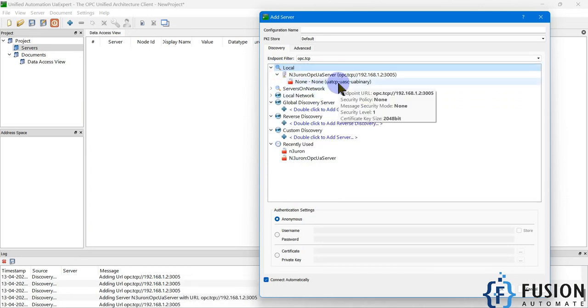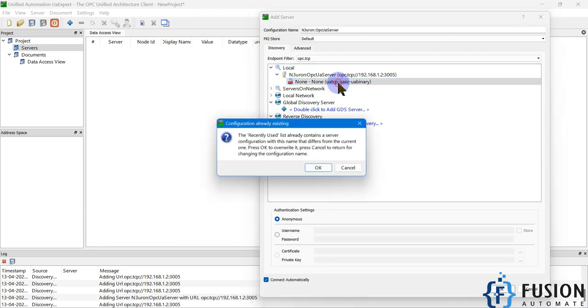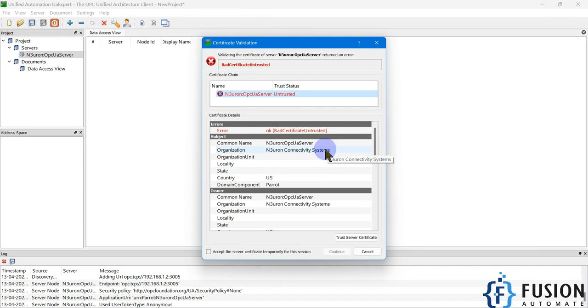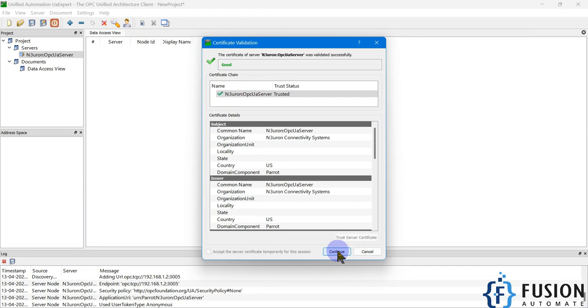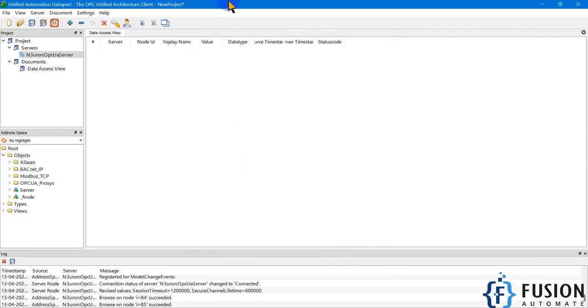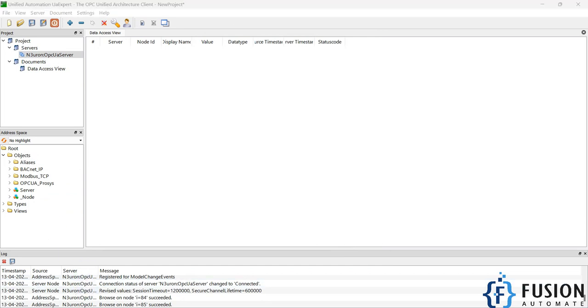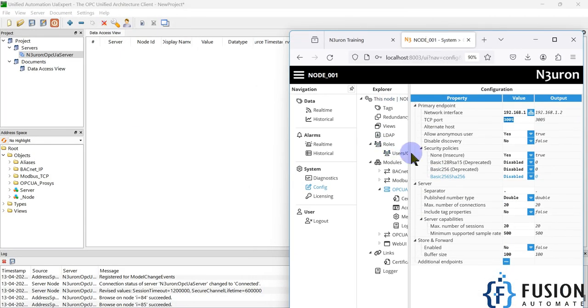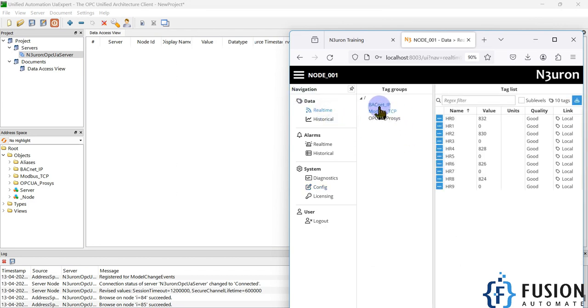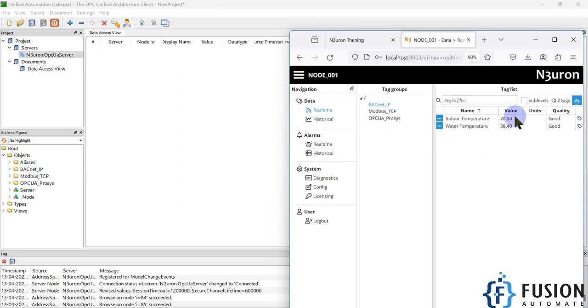After disabling extra policies, only the None policy remains. Double-click to connect — it will ask you to trust the server certificate, so click Trust Server Certificate and press Continue. Our OPC UA server is now connected and the entire address space is visible. You can see a folder for BACnet IP and a folder for Modbus TCP in the address space.